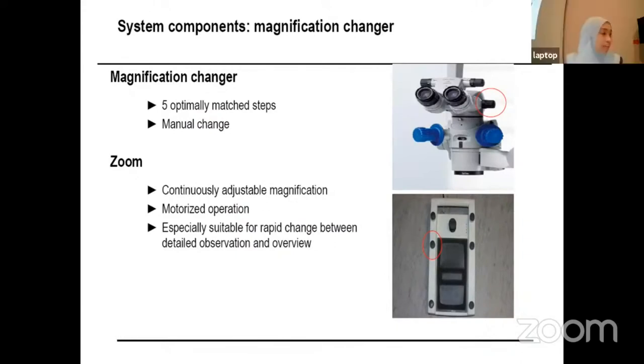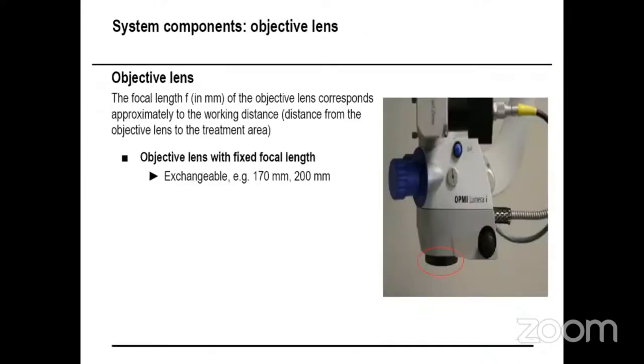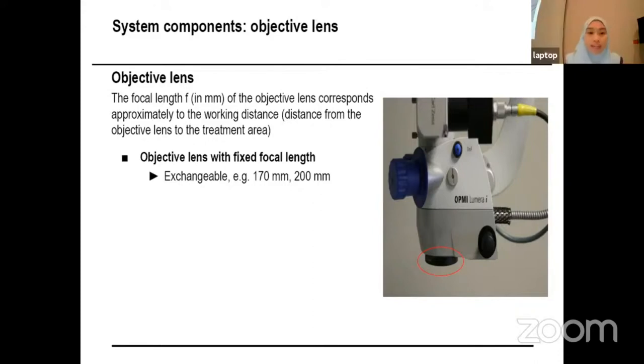The magnification changer typically has five optimally matched steps that can be changed manually, and the zoom is controlled by the foot pedal, which provides continuously adjustable magnification. For the objective lens, the focal length corresponds approximately to the working distance — that is, the distance from the objective lens to the treatment area. Objective lenses have a fixed focal length, usually either 170 or 200 mm.